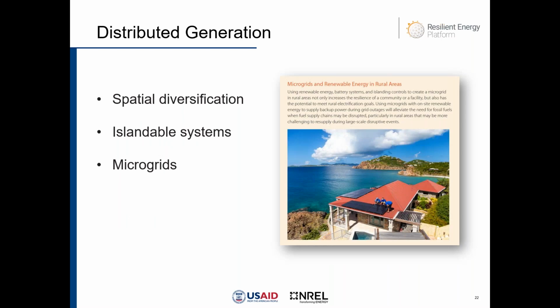Decentralizing energy sources is another technique used to enhance power system resilience. On-site renewable energy generation or other generators can reduce disruption related to a grid outage, mitigating the impacts of a long-term outage. Microgrids are typically implemented where on-site renewable energy is combined with energy storage to support resilience. Systems designed to operate in islanded mode can be isolated from a larger grid, allowing the system to generate and distribute energy on-site in the event of a power outage.